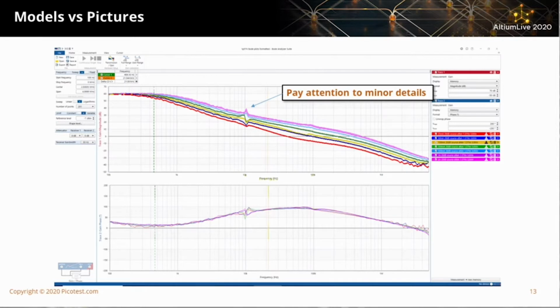But what I want you to focus your eye on is this little tiny wiggle that shows up right here where the arrow is. That's easily overlooked, but that actually tipped us off to the fact that there was an inner loop in this power supply, and that inner feedback loop was unstable and showing up as this little divot. Now that divot could have been noise, except that noise generally doesn't repeat itself so accurately, so it wasn't likely that that was noise. But things like this actually get written off quite frequently by engineers as anomalies, oddities, or other random noise events when they're not. And so you need to be really attuned to those things when you're making measurements. I'm going to show you a couple of other examples of that a little later on in this presentation.